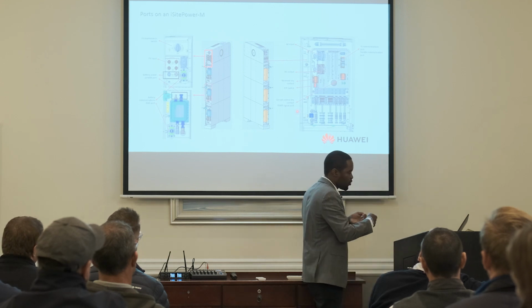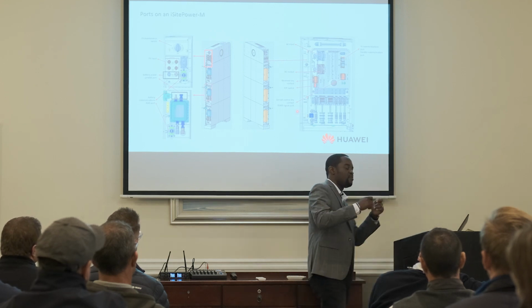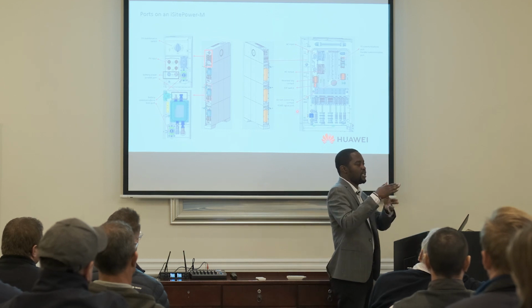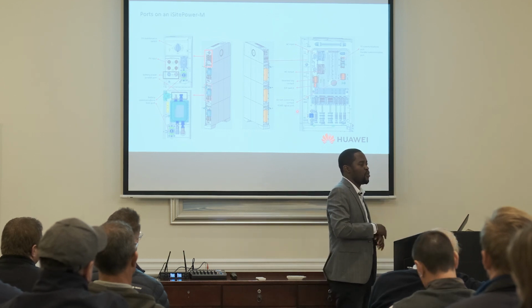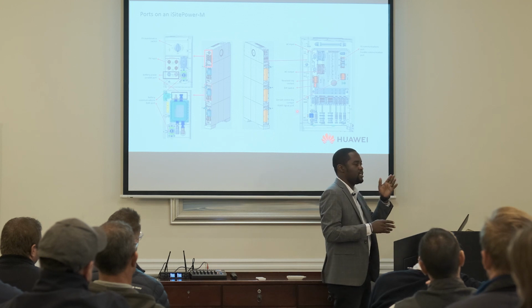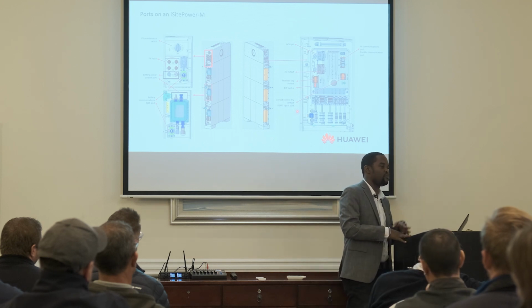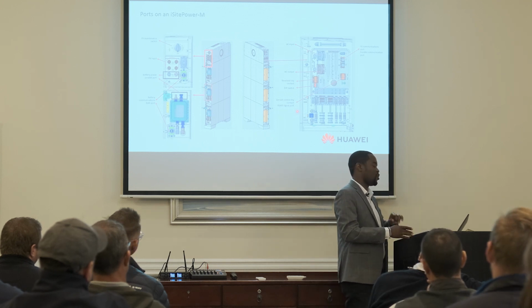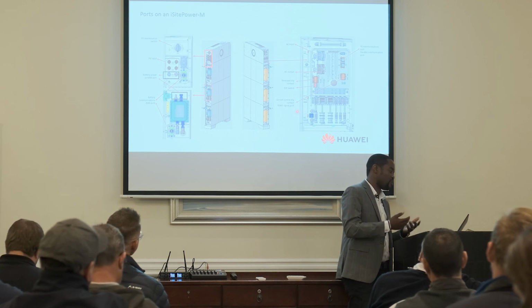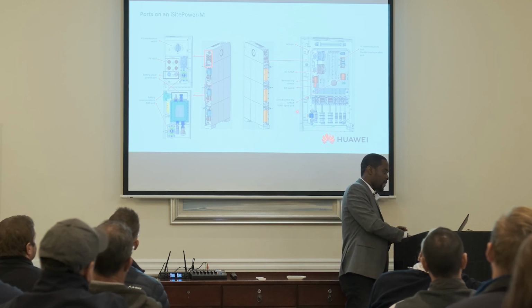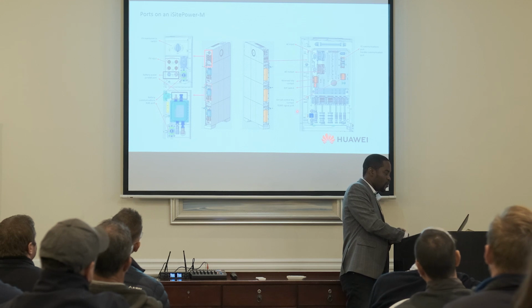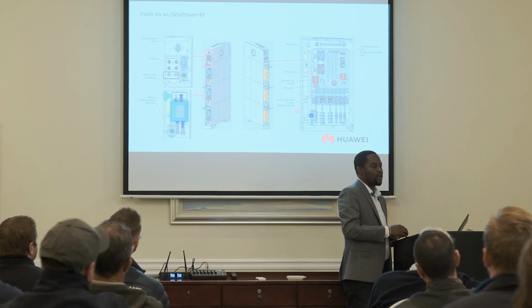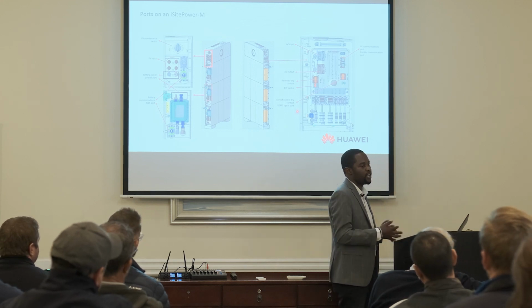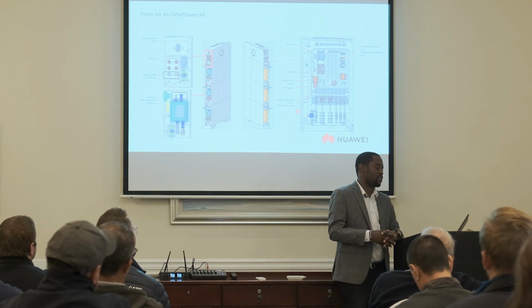Let's say you took out all the connections, you do the terminations. When you're coming to the inverter, if you make a mistake, then it won't allow you to make that mistake, because the AC input can only go to the AC input slot, and the AC output cannot go to the AC input slot. So you are protected there even if you make a mistake, right? On the strings, if you reverse your polarity on the strings, the inverter will give you an alarm. You won't damage your system.